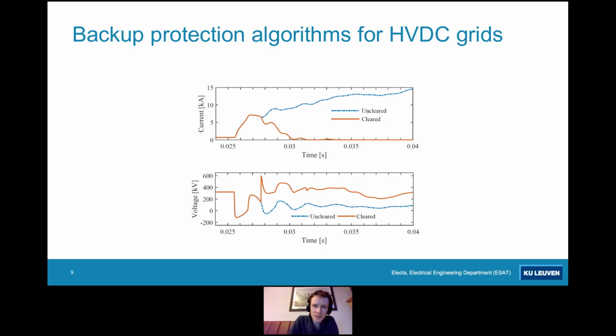For these algorithms, we could look at the traditional AC approach. In this approach, we wait long enough so that we know that the breaker should have reacted, and then we measure the current. So if the current through that breaker at that time is zero, we know that the breaker has acted correctly. If it is not zero, we know that it has failed.